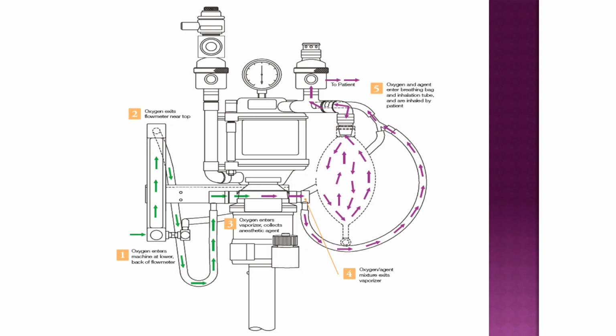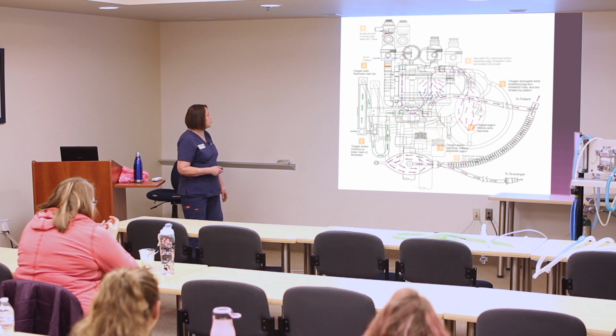I will also tell you that I'm not a big fan of these matrix machines, and the reason for that is most of the time whenever you meet an anesthetic machine you're not familiar with, you're going to be able to guess that the bag is on the expiratory side. But for whatever reason they decided to make the bag go on the inspiratory side of these machines, and that's why when you look at one, they're labeled really thoroughly that the bag is inspiratory, the other side is expiratory, because it's counterintuitive to the vast majority of machines that you will find out there. So that is the flow of gas through the circle system.